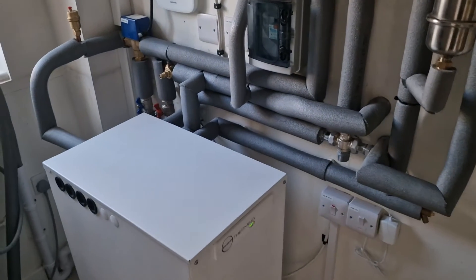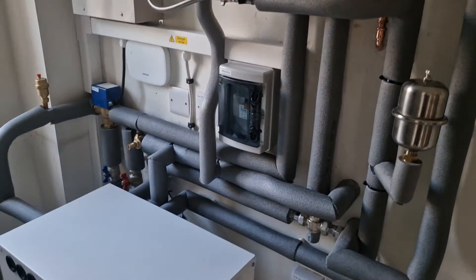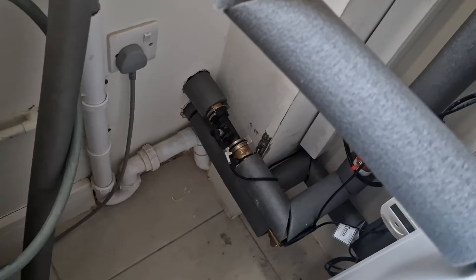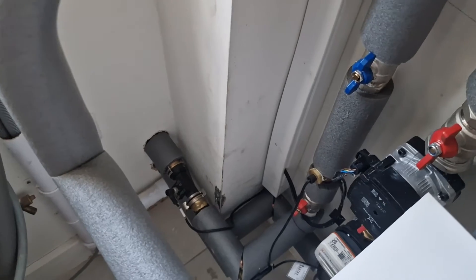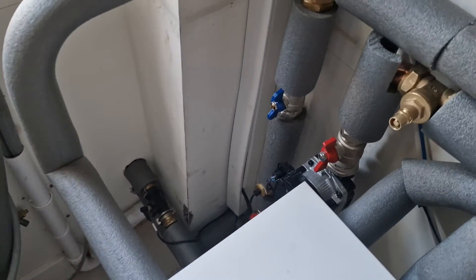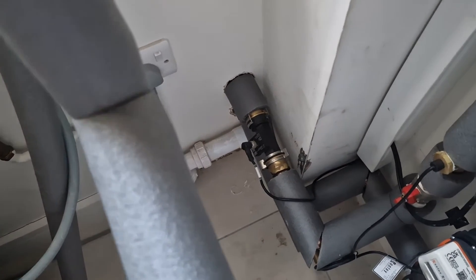As you can see, there's no low loss header or volumiser — just straight connected into the pipes. It needs some painting but that's fine. You can see where the flow and return come from outside the house — it's quite close to the unit, which means heat losses are minimized. Everything is insulated as well. You have the flow sensor for the Samsung here.